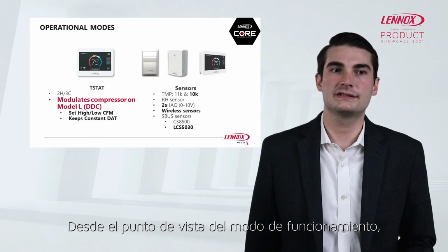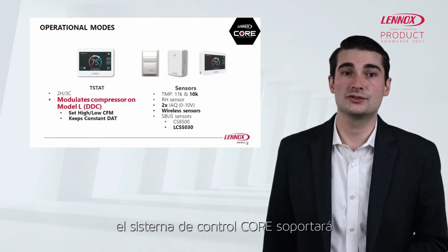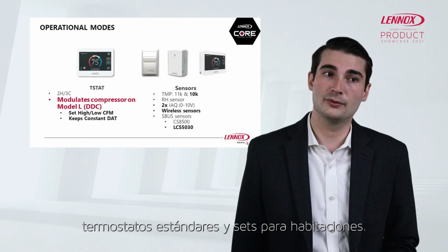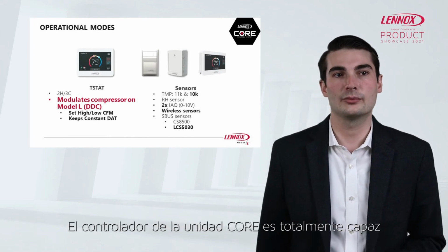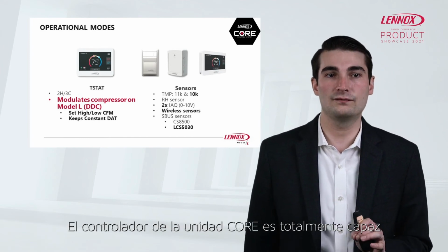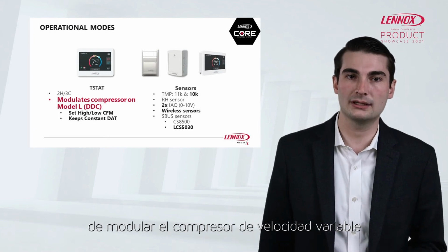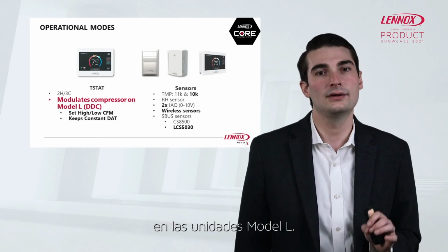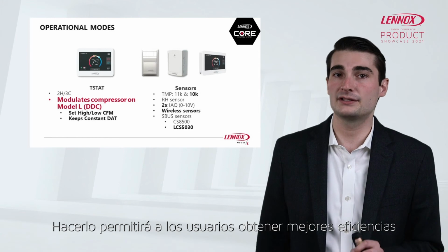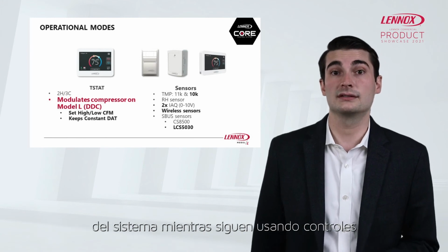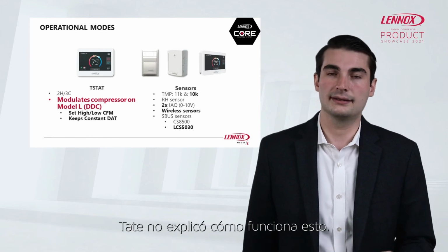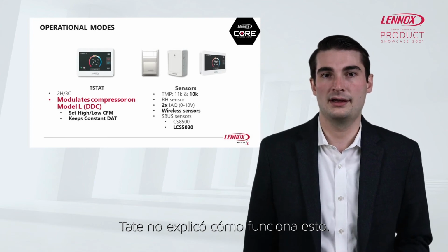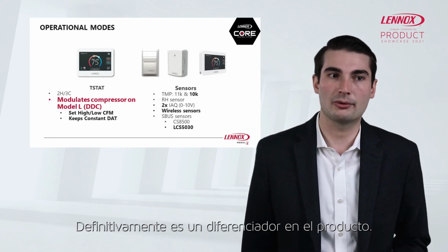From a mode of operation standpoint, the Core control system supports standard thermostat and room sensor modes. When using thermostats, the Core unit controller is fully capable of modulating the variable speed compressor on Model L units. This allows users to get better system efficiencies while still using simple thermostat controls. Tate laid a bit of that out and how it works - it's definitely a differentiator in the product.